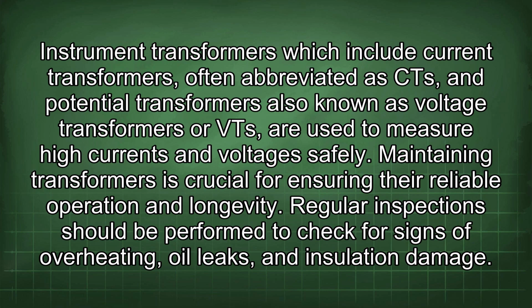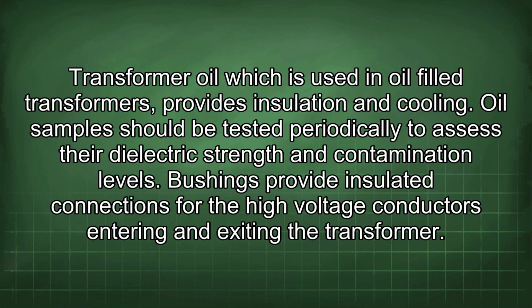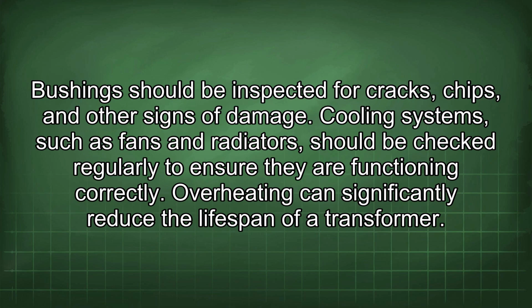Maintaining transformers is crucial for ensuring their reliable operation and longevity. Regular inspection should be performed to check for signs of overheating, oil leaks, and insulation damage. Transformer oil, which is used in oil-filled transformers, provides insulation and cooling. Oil samples should be tested periodically to assess their dielectric strength and contamination levels. Bushings provide insulated connections for the high-voltage conductors entering and exiting the transformer. Bushings should be inspected for cracks, chips, and other signs of damage.